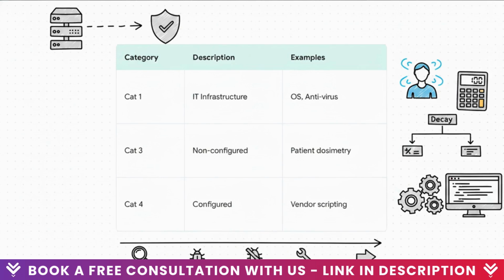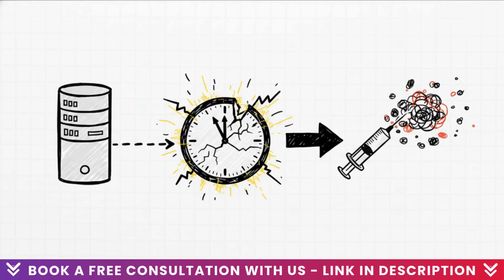It comes with huge testing burdens, bug reporting protocols, and strict functional tests during installation just to prove those algorithms are completely flawless. And here is why all this testing matters. The highest risk software failures aren't always giant, fiery system crashes. It could be something as mundane as an incorrect system time setting. Remember, our inventory is decaying by the minute. If the server clock is off by even a tiny bit, every single decay calculation gets ruined. That leads to incorrect dosages being drawn up and injected into patients. A minor bug can totally alter an exam result.